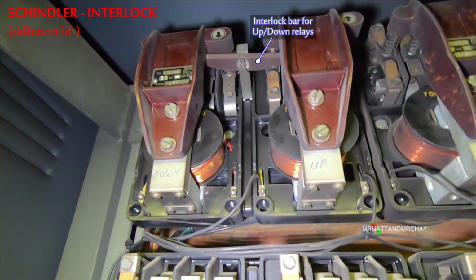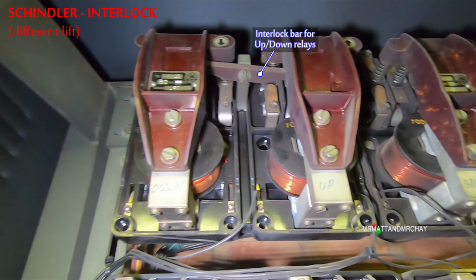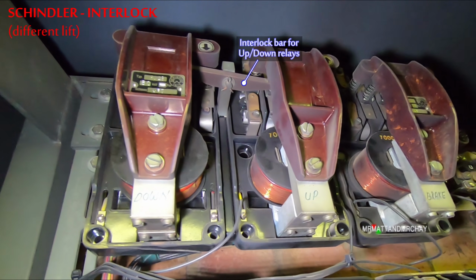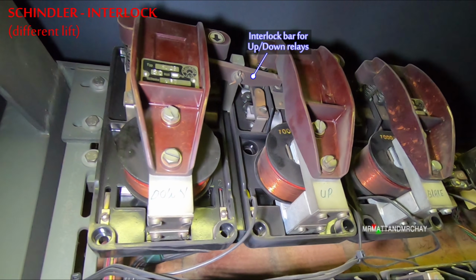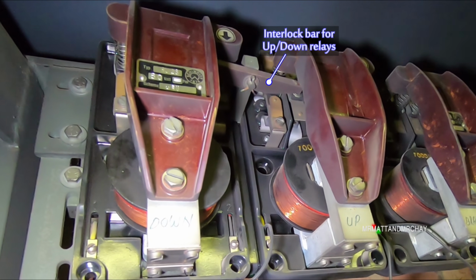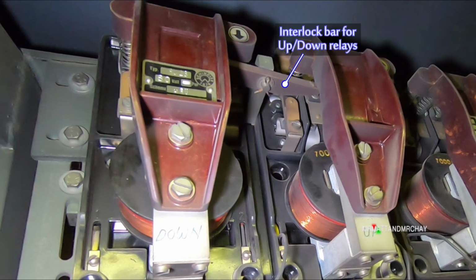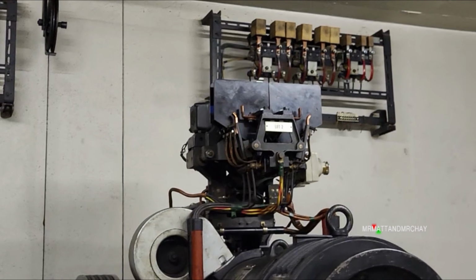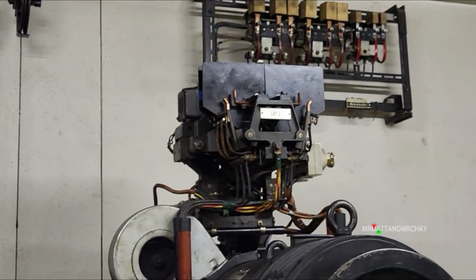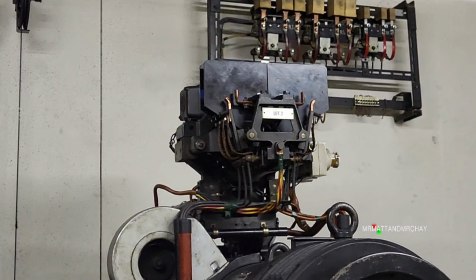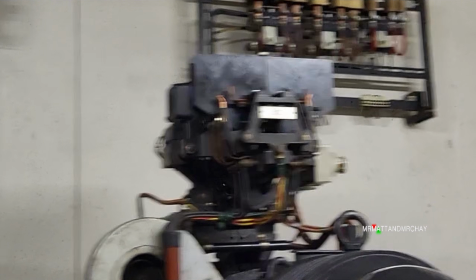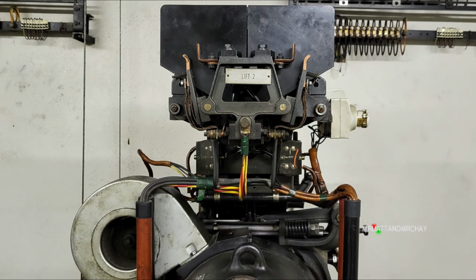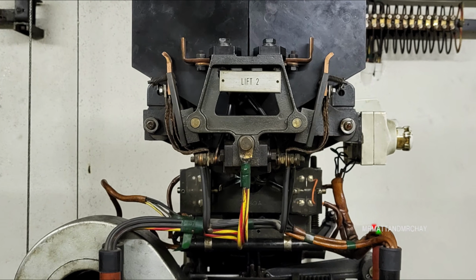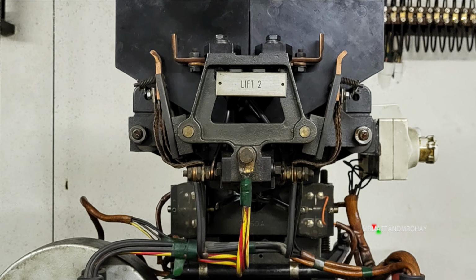Between relays, there is a bar that pivots in the middle. When the up relay is on, the bar is pushed, and the other end sticks up and physically stops the down relay from coming on, and vice versa. On the left and right here, we can see the equivalent of the up-down relays that I've just shown you. Schindler has used the brake motor to physically control the intended direction of the main motor.